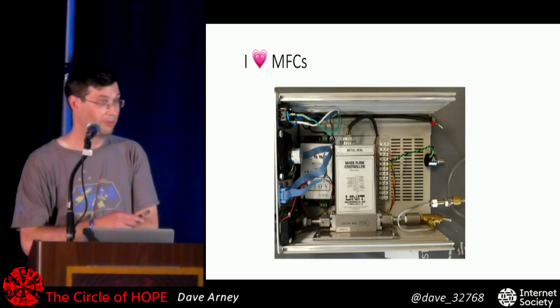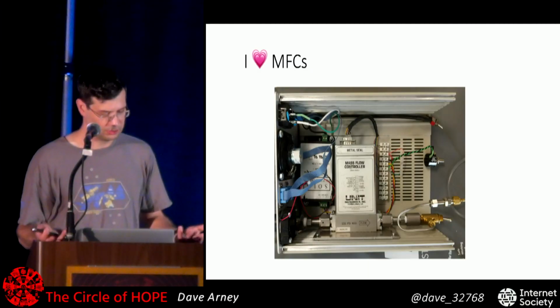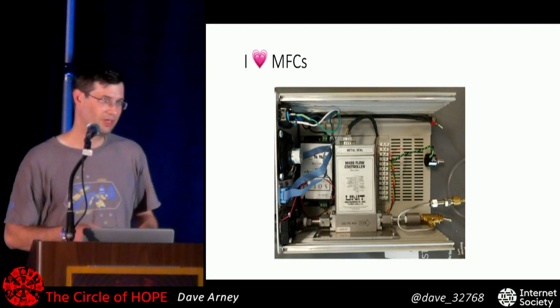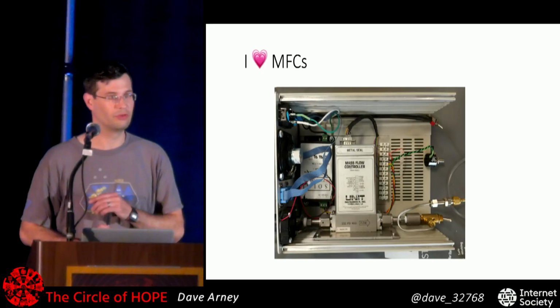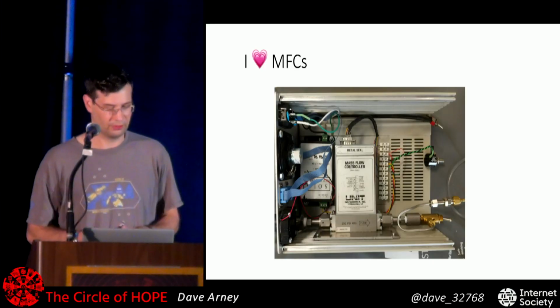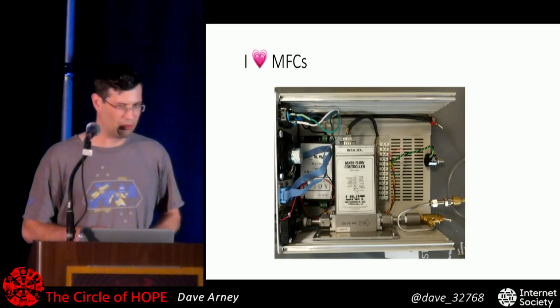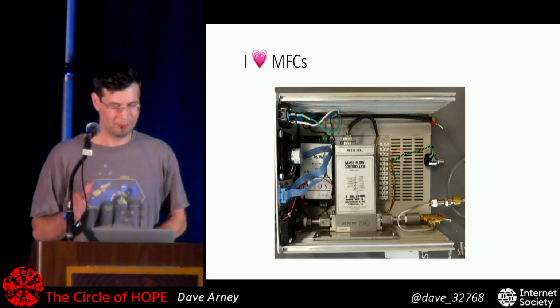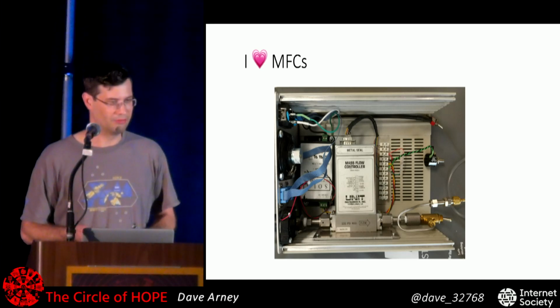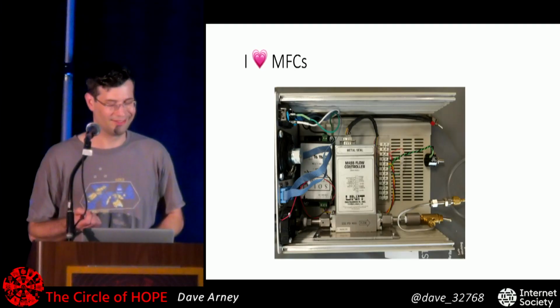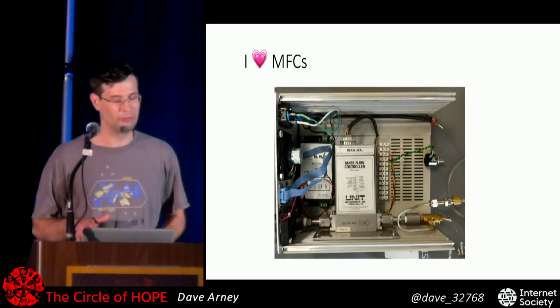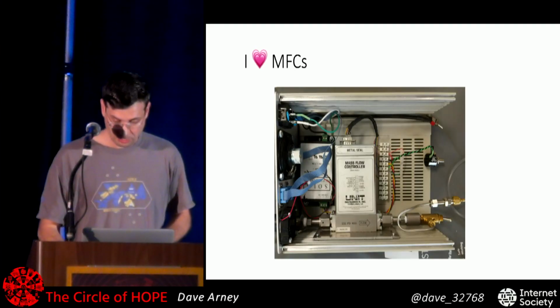There are different kinds that operate at different speeds, and they tend to be calibrated for different gases — you'll see mass flow controllers for nitrogen, for CF4, for hydrogen. Modulo what the seals are made of and how corrosive your gas is, they'll usually work with anything, and there are calibration adjustments you can do.